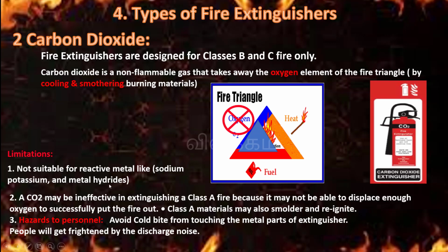It also has a hazard to operating personnel who are handling the CO2 fire extinguisher. They should take care during fire extinguishing. Avoid cold burns from touching the metal parts of the extinguisher. People may also get frightened by the noise of the discharge.